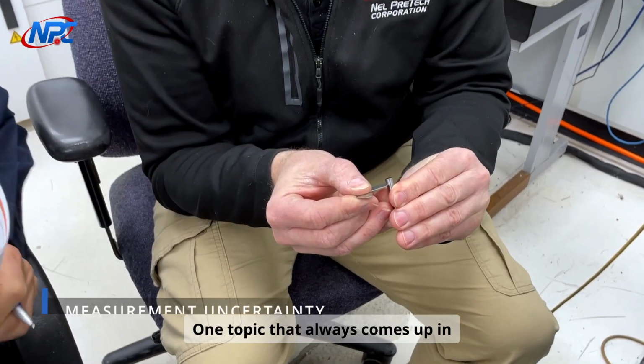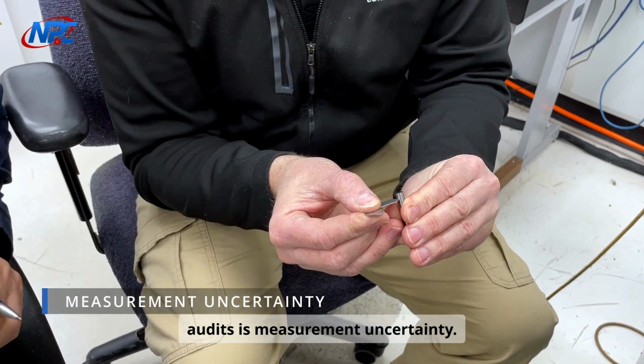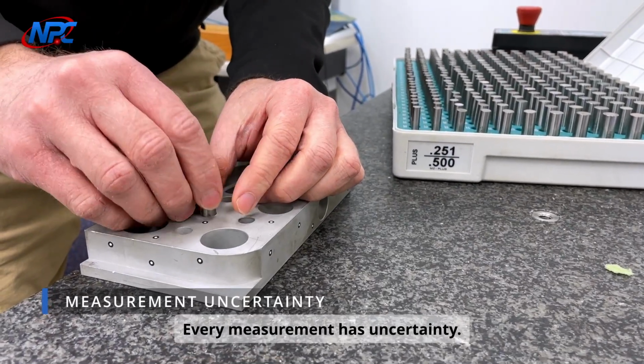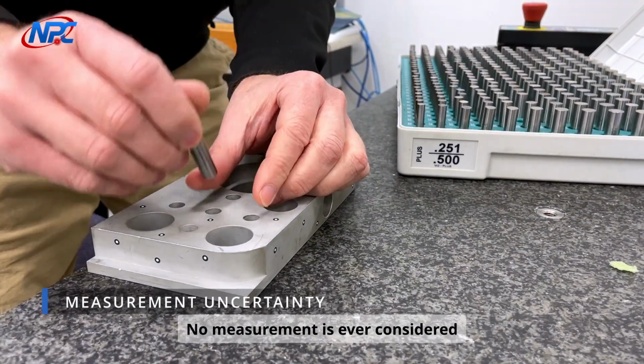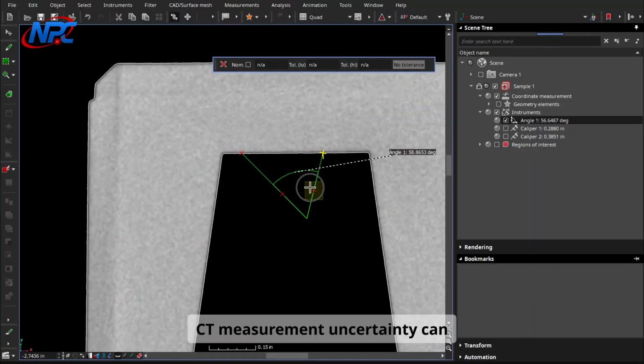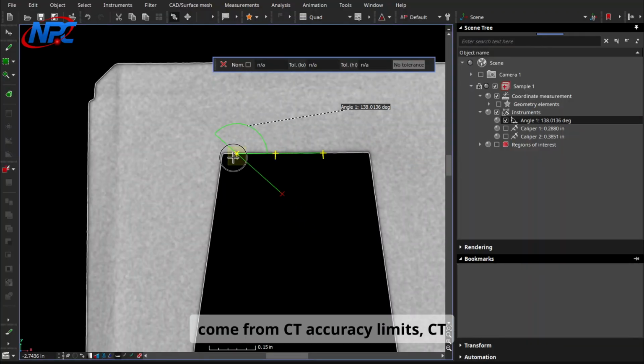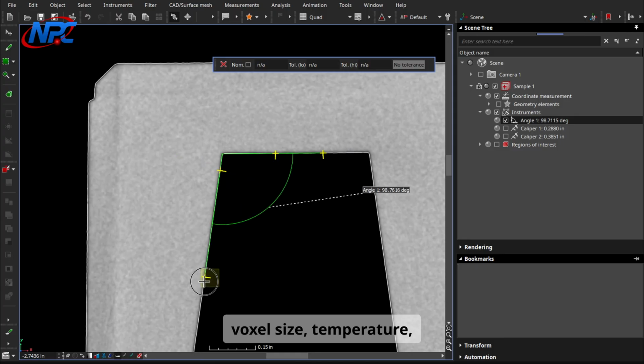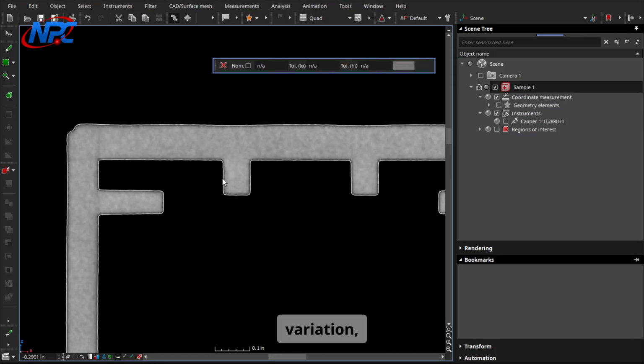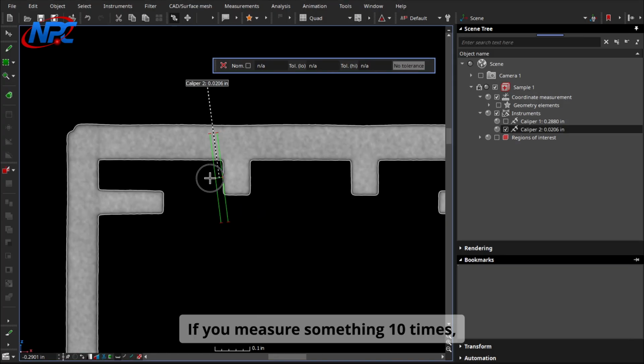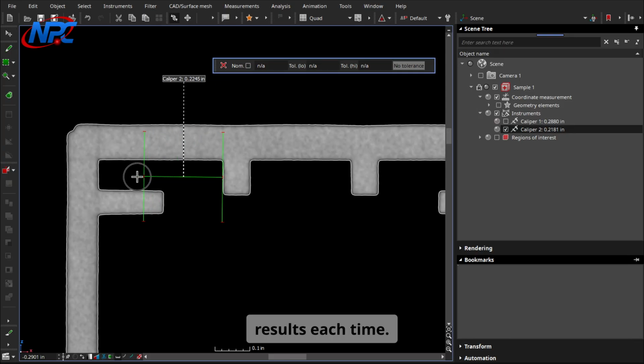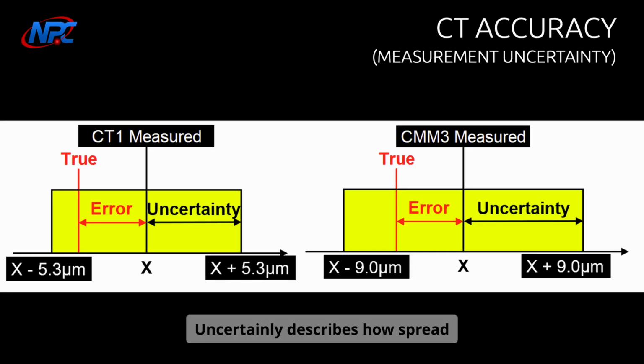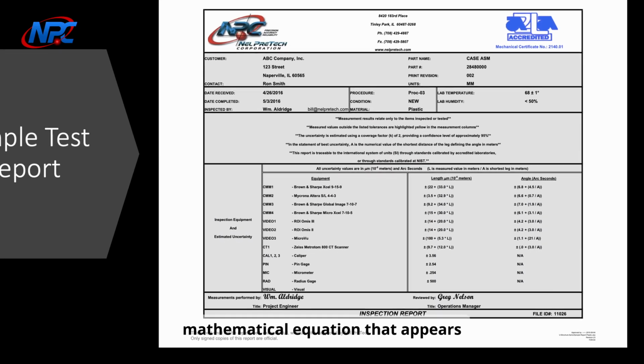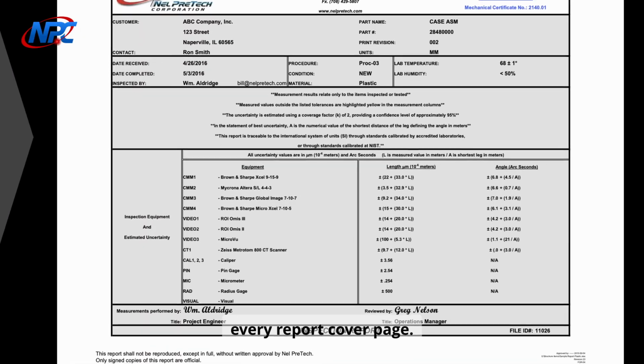One topic that always comes up in audits is measurement uncertainty. Every measurement has uncertainty. No measurement is ever considered perfect. CT measurement uncertainty can come from CT accuracy limits, CT voxel size, temperature variation, vibration, etc. If you measure something 10 times, you can get slightly different results each time. Uncertainty describes how spread out those results are. For CT, that measurement uncertainty is defined as a mathematical equation that appears on every report cover page.